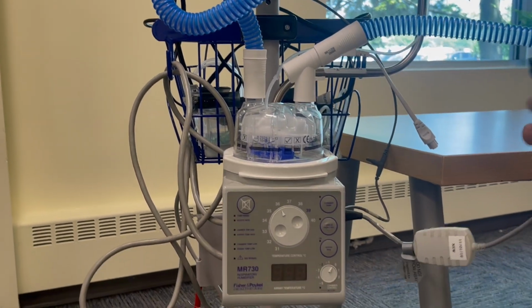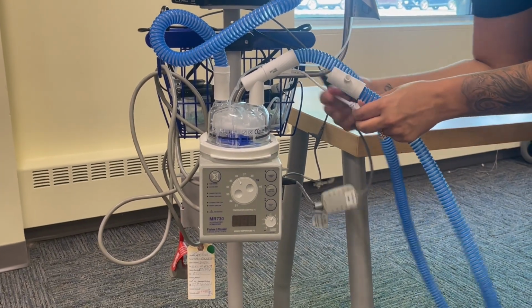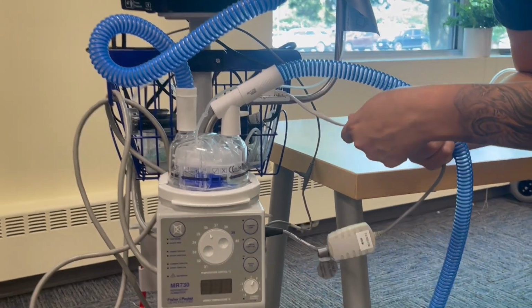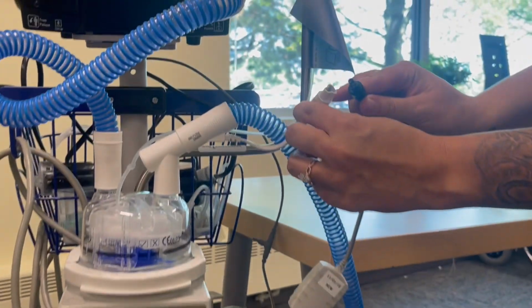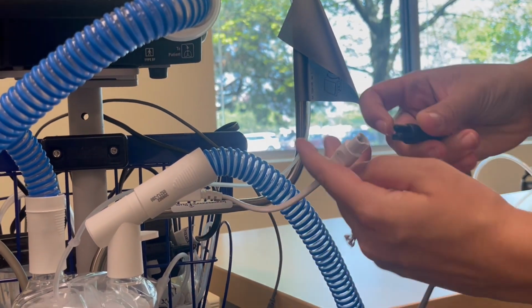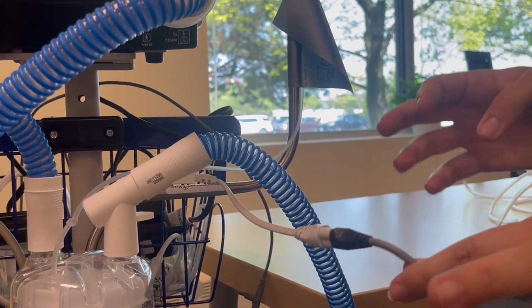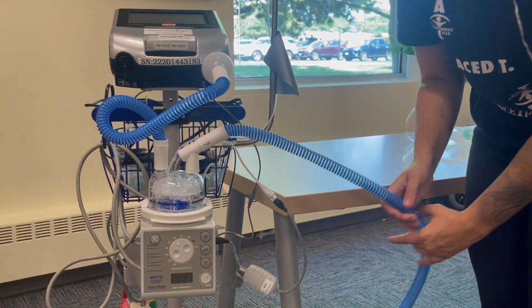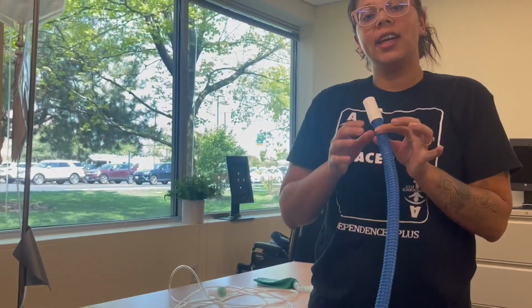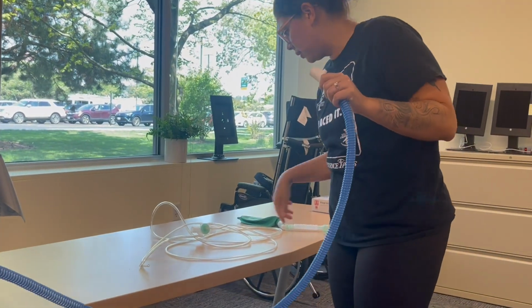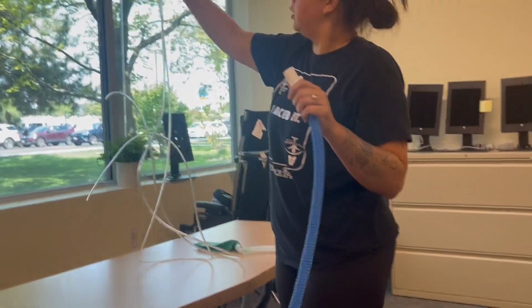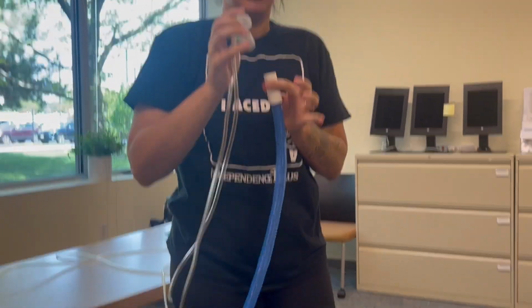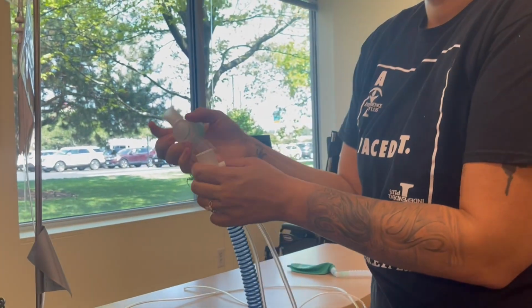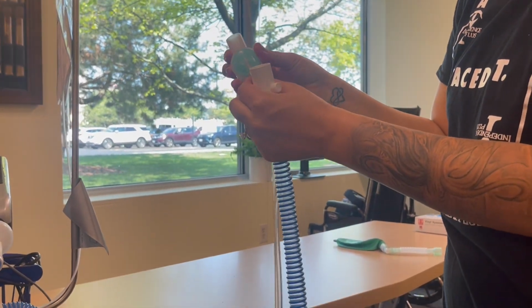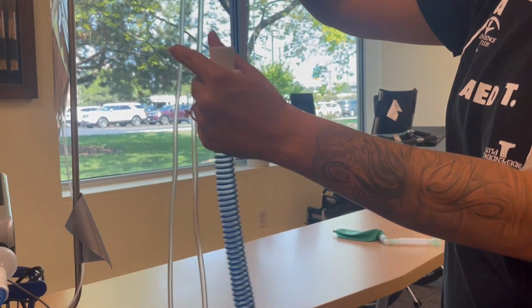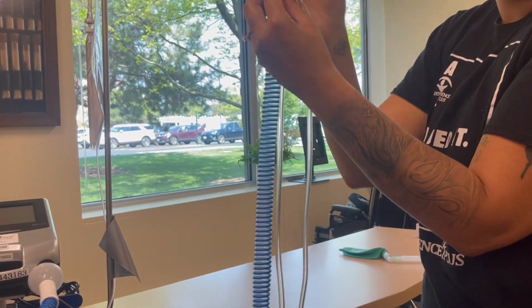And now I can connect this adapter to this tail that's hanging off of the tubing. Sorry, my hand's in the way. So here you can see there's a 2-prong that's gonna plug into the 2 prongs here. So now this is connected and this will work for me. My tubing is gonna get connected to my exhalation valve. So here is my exhalation valve. This is gonna connect, the wires are gonna run towards the ventilator. So if you look, the wires are running down. So that's how I know that I need to connect it this way into the tubing.